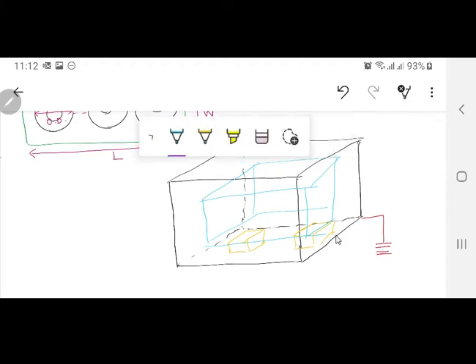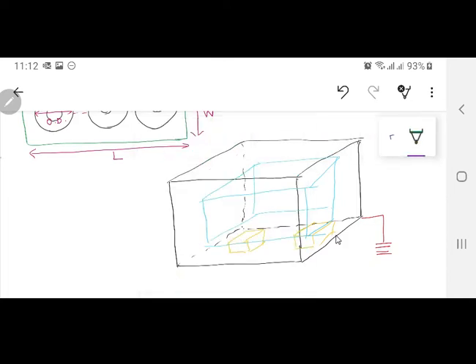One thing very important: when you do this, the oil is not going to be filled up to 100%. Why? Because we know the transformer is going to be heating up and the oil will expand, so we have to keep some space.